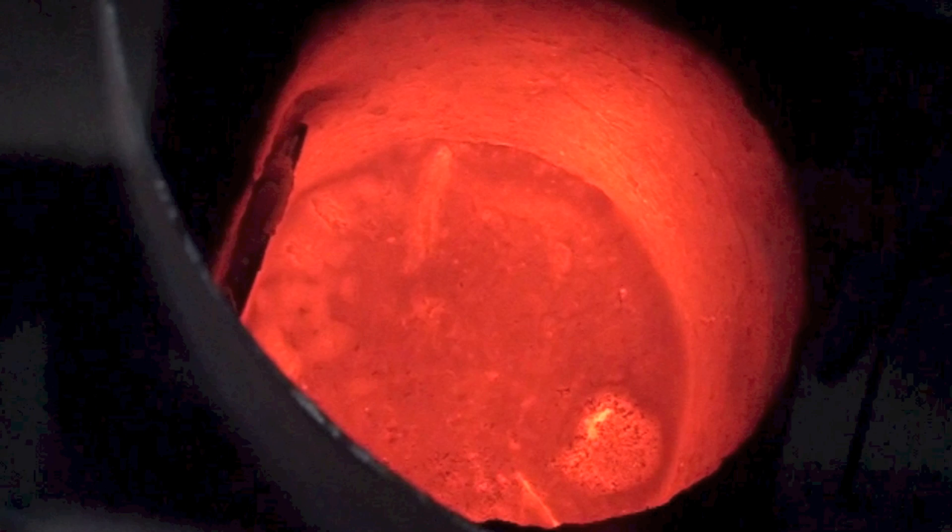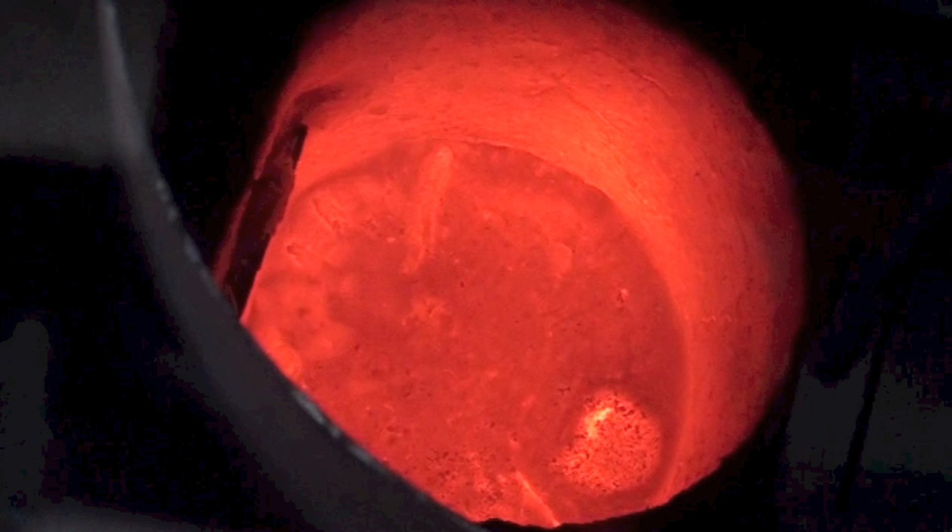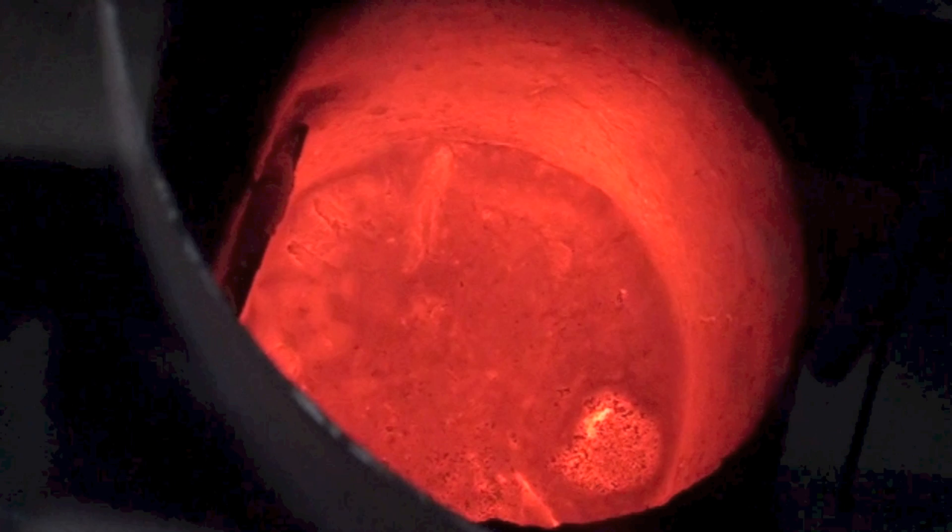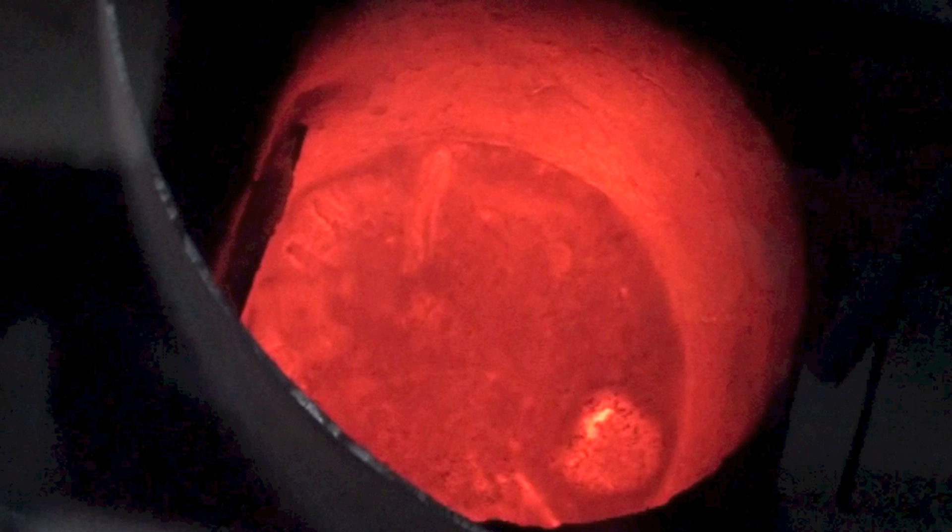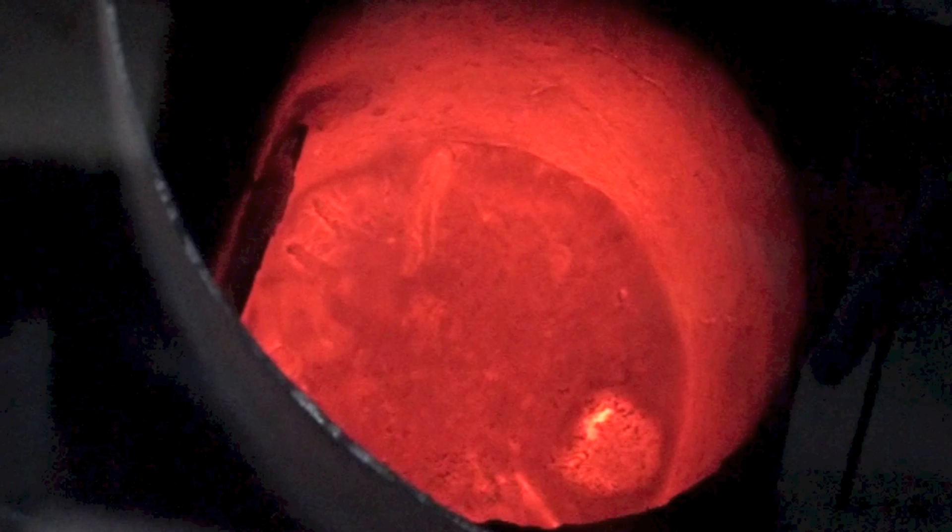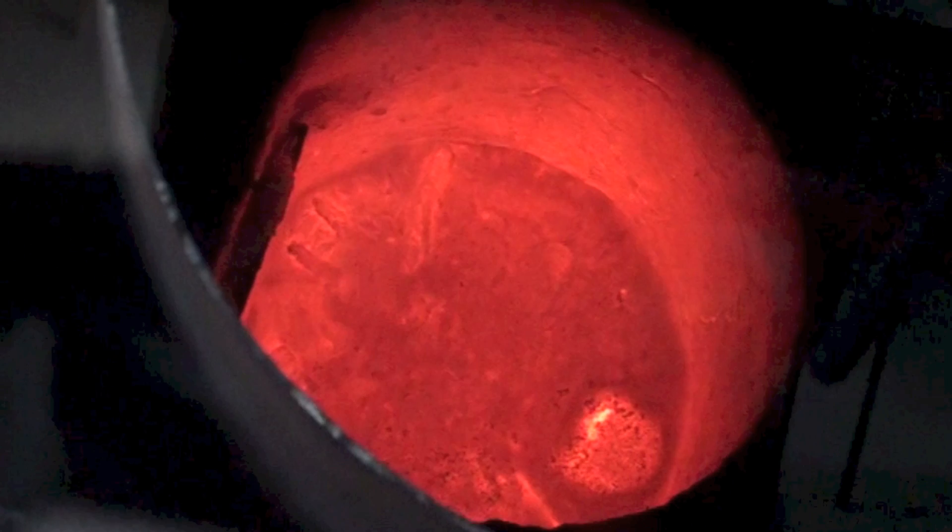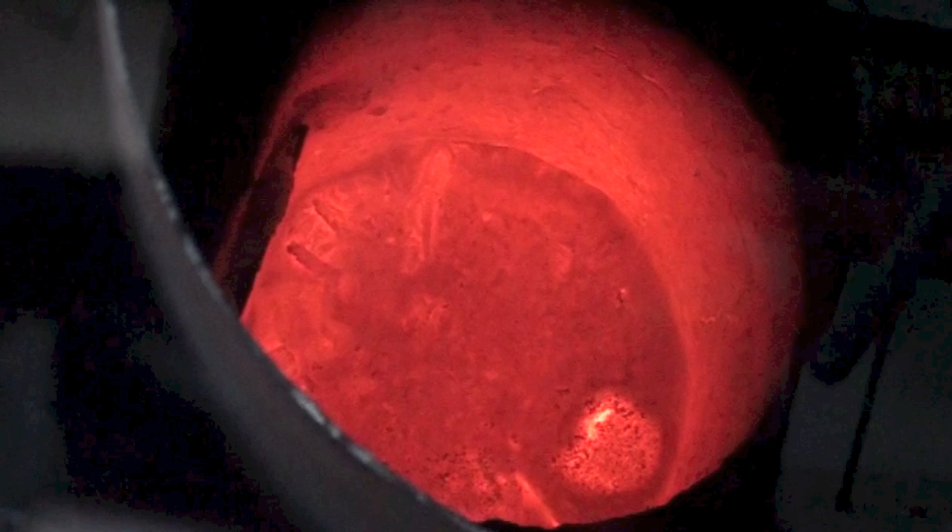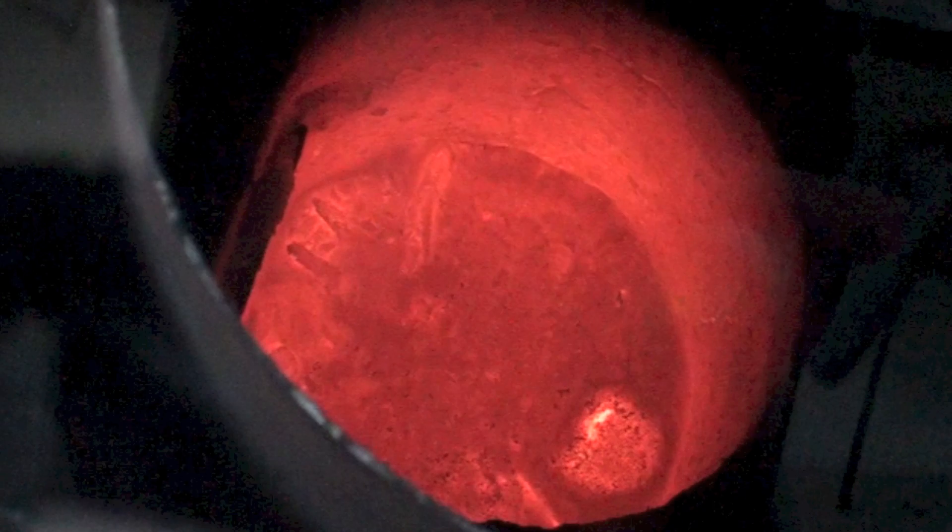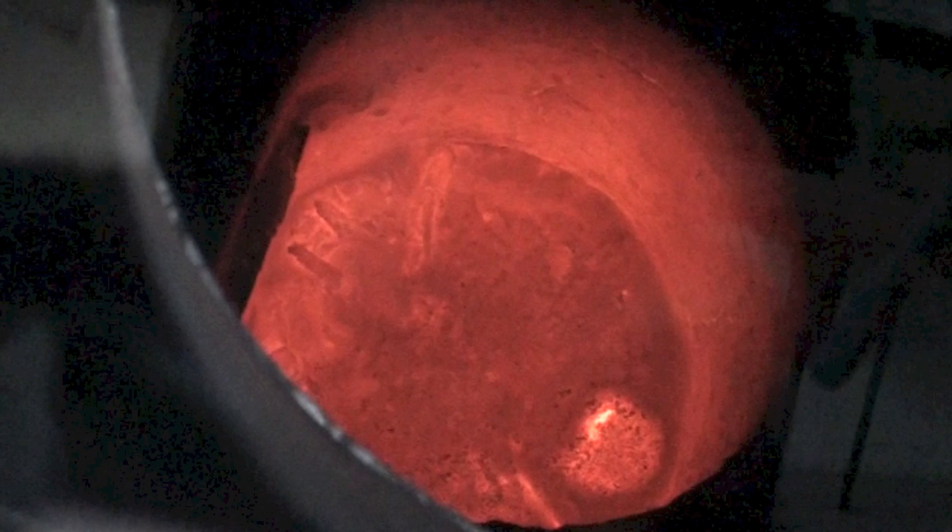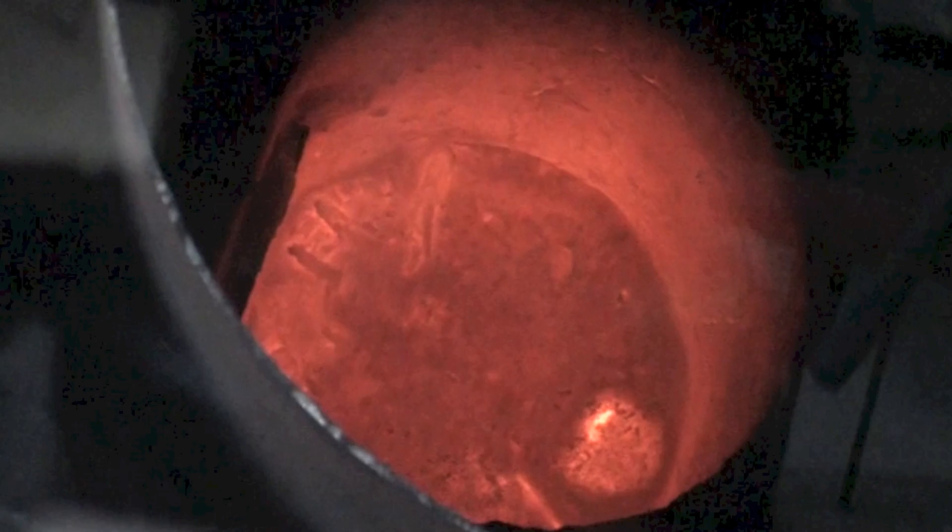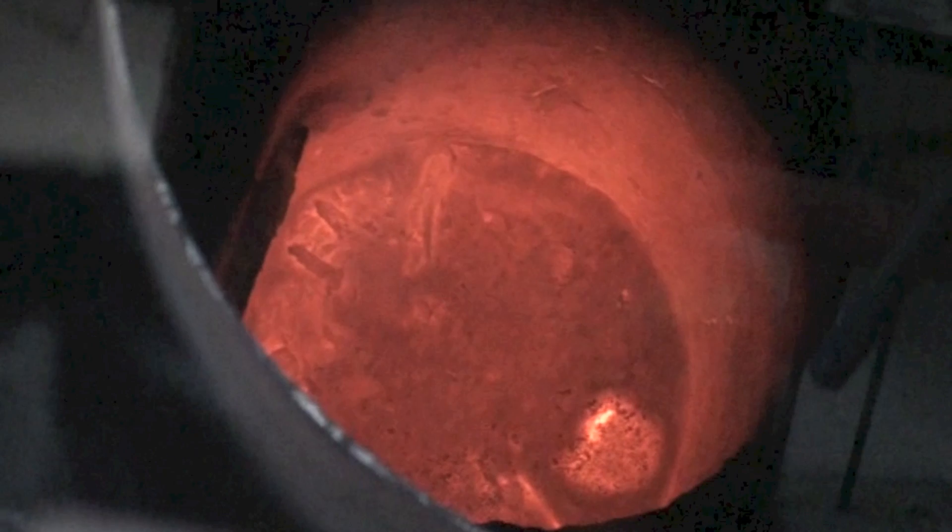That combustion chamber is supposed to reflect heat back into the fire and complete the burn. The atomized oil needs to be evaporated before it can burn, so what it does is it reflects that heat back in there and you want as much heat as possible in the flame because you want to make the most complete burn you can get.